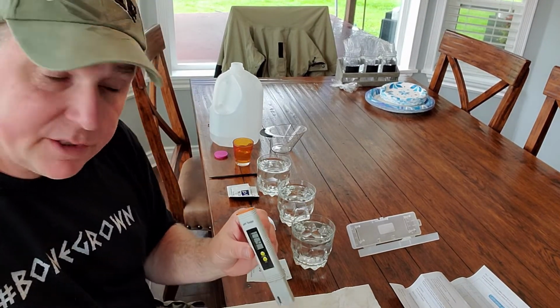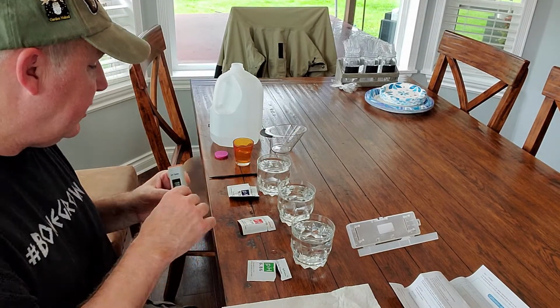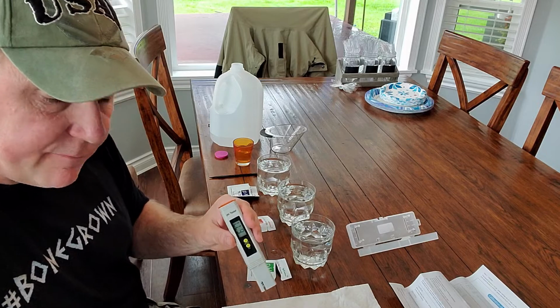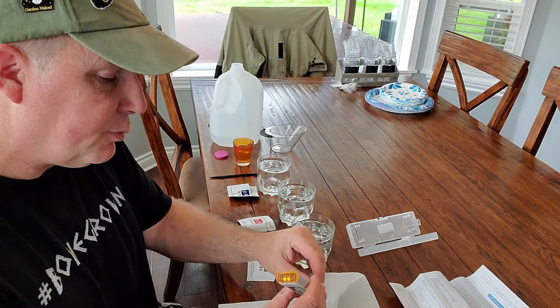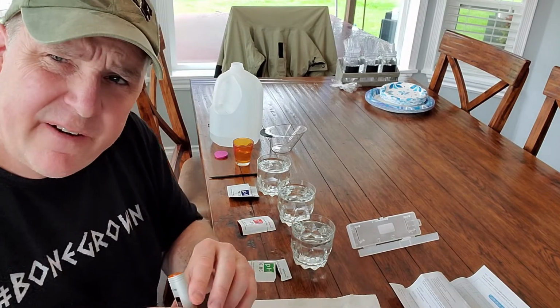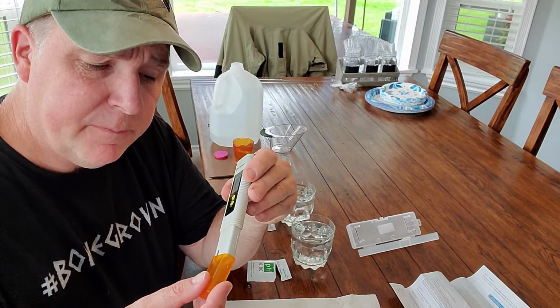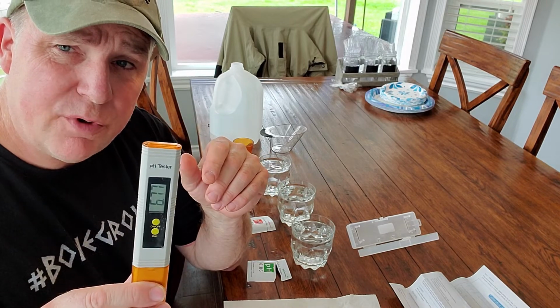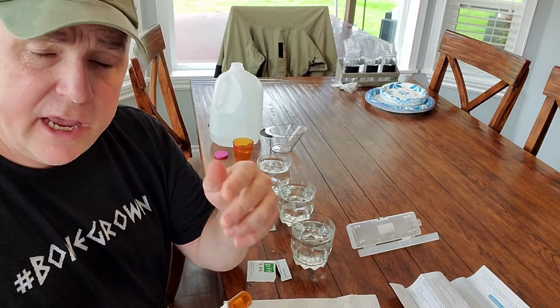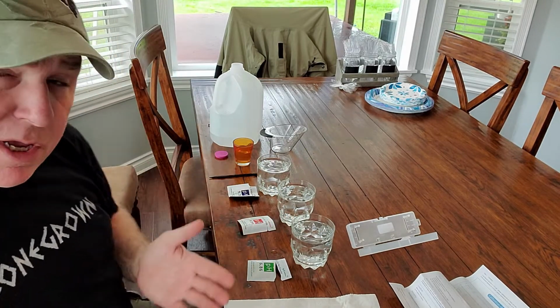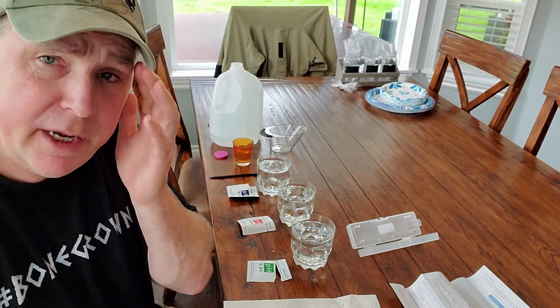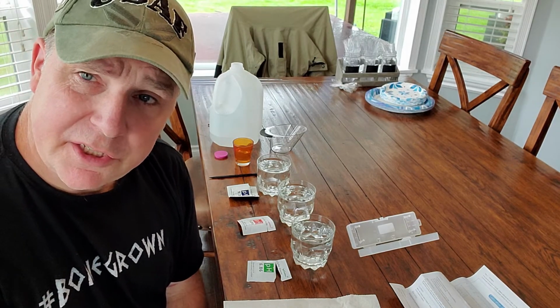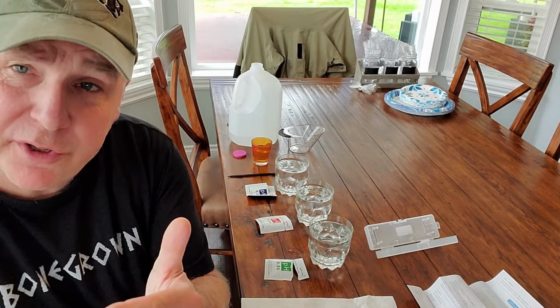Sometimes you have to dial these back in. You should never think that your pH meter is always just perfect. If for whatever reason you start getting funky readings, it's easier to check it and make sure it's right than to let it go and give erroneous readings. Because for me, when I'm dealing with pH for my soil, and even pH for my hot sauces, you have to make sure that pH is correct. If you don't, you could hurt somebody, or you could hurt your plants.